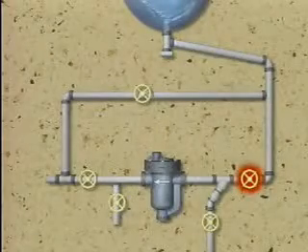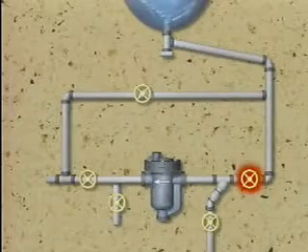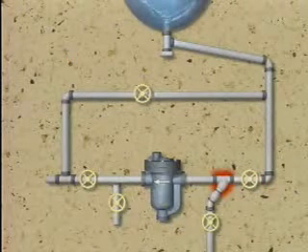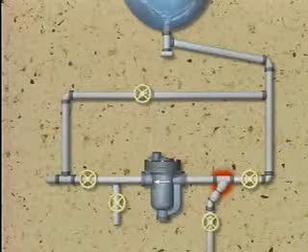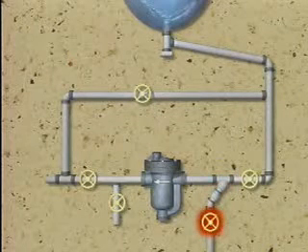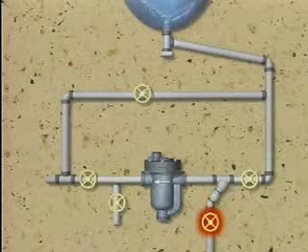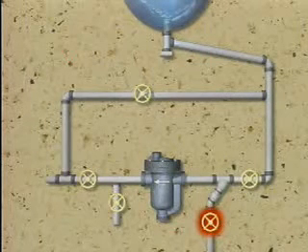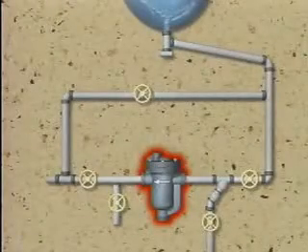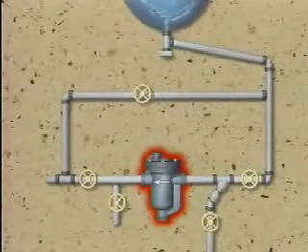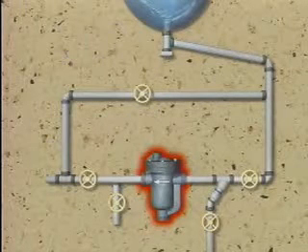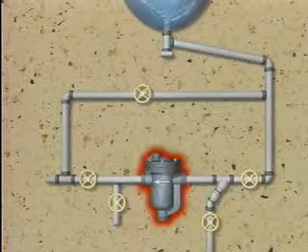An inlet valve isolates the steam trap inlet from the steam line. A strainer near the inlet valve prevents dirt and scale from entering the steam trap. A blow-down valve on the strainer can be opened to enable the strainer to be cleaned or blown down by directing flow back through the strainer to the atmosphere. The steam trap itself drains condensate from the system while preventing the escape of live steam, and may also remove non-condensable gases and some air.